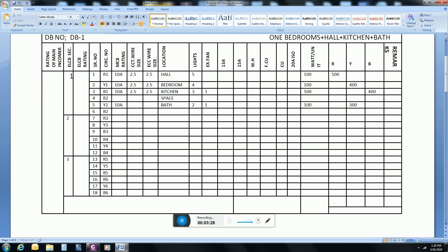The MCB for the bath circuit will be 10 ampere, circuit wire size 2.5mm, and ECC wire size 2.5mm. For the remaining space on this phase, the breaker will be 10 ampere as well. There is no additional load to connect on this phase.